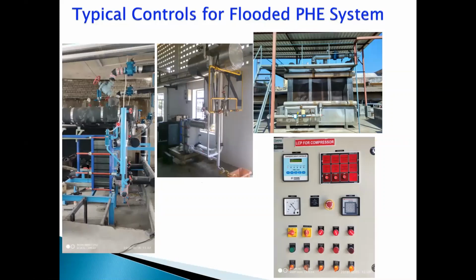You can see here a plate type heat exchanger provided with a liquid level control, a back pressure regulating valve to maintain a constant pressure at the evaporation, a liquid feed solenoid valve, and a hand expansion valve.